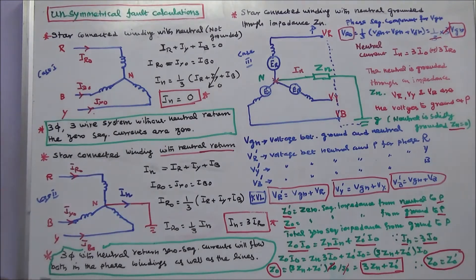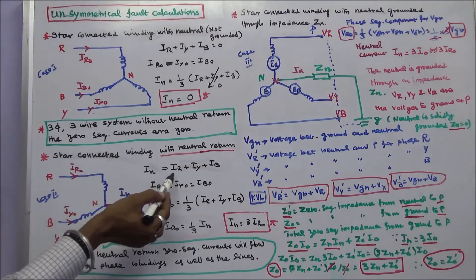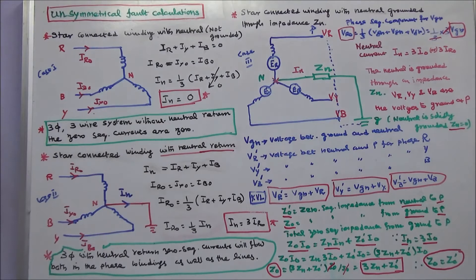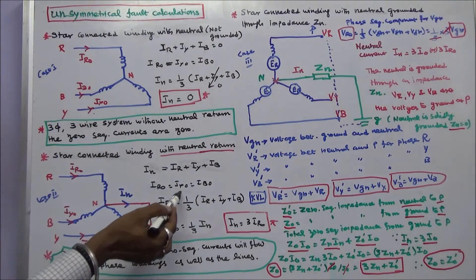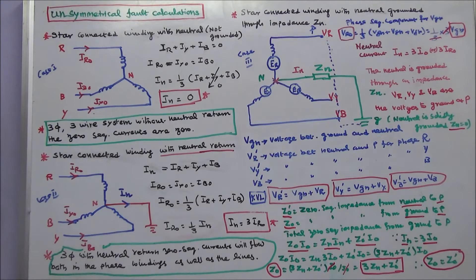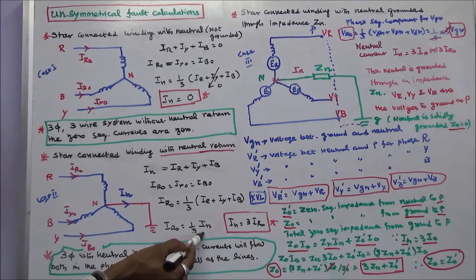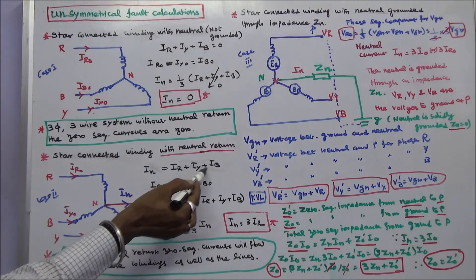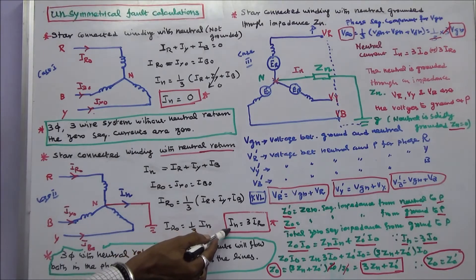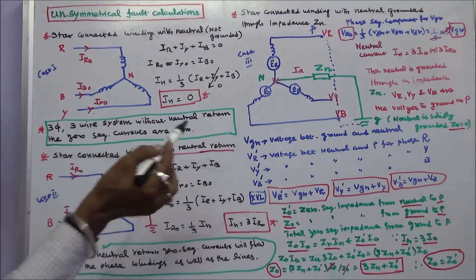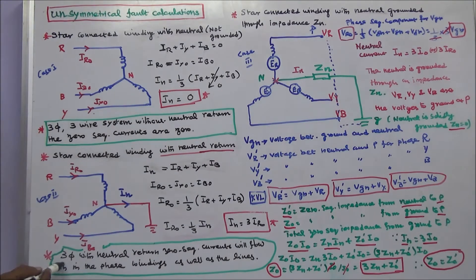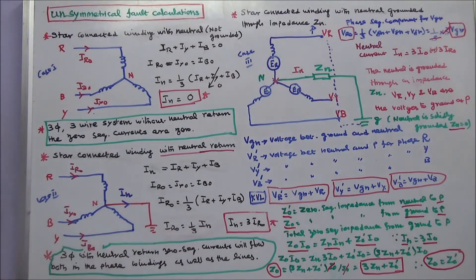Case 2: star-connected winding with neutral wire grounded. Here neutral current IN equals IR plus IY plus IB, and IR0 equals IY0 equals IB0. Therefore IR0 equals one-third times IN, meaning the neutral current IN equals 3 times the zero-sequence current IR0. In a three-phase system with a neutral wire, zero-sequence current will flow both in the phase windings as well as the lines.